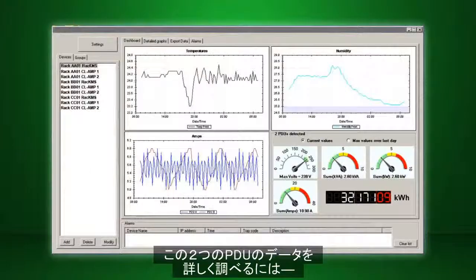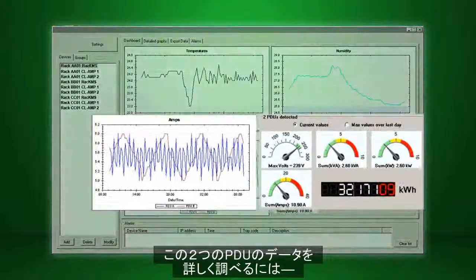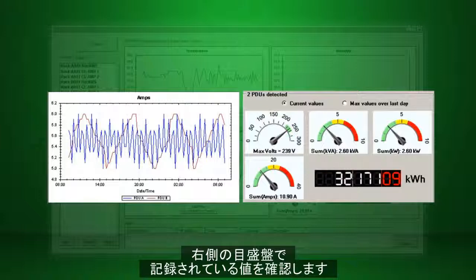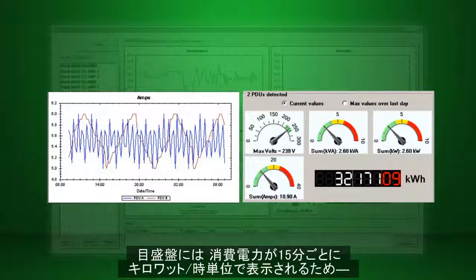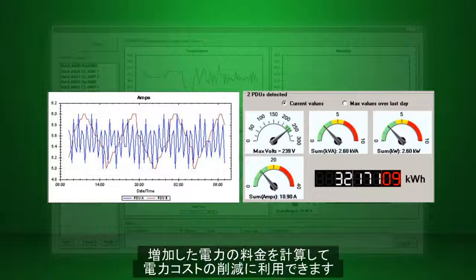The data being monitored from these two PDUs are further detailed in the dials displayed to the right of the power draw display to show the values being recorded. The numerical display here shows kilowatt-hour consumption every 15 minutes continuously throughout the day, offering the ability to calculate increases in kilowatt-hours and generate billing information to reduce energy costs.